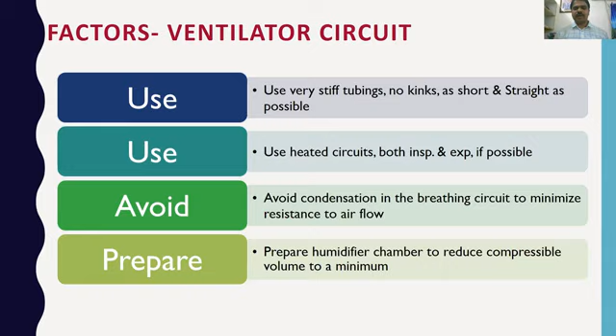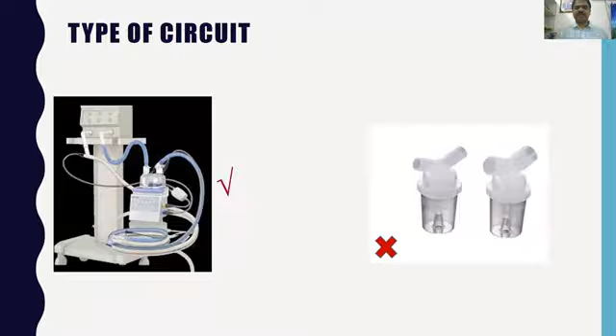As I was just mentioning, the type of circuit. As you can see here, the inspiratory circuit, the blue one, as well as the expiratory circuit, both of them have an inline heating mechanism. The earlier versions don't have this kind of thing. They used to have a water trap, earlier in both the inspiratory as well as expiratory circuits, which is not desirable, because it will lead to volume loss. Also, effective tidal volume delivery won't be good. And another important thing is, if there is any leak while fitting this water trap, it will again hamper the high frequency delivery.